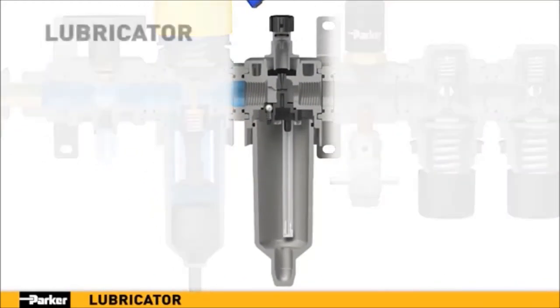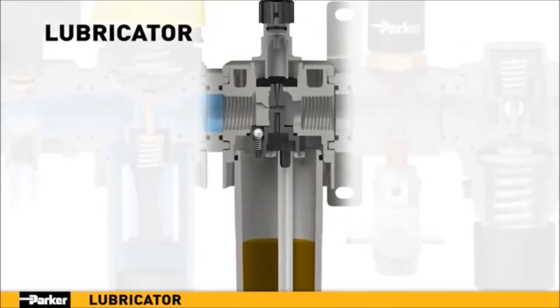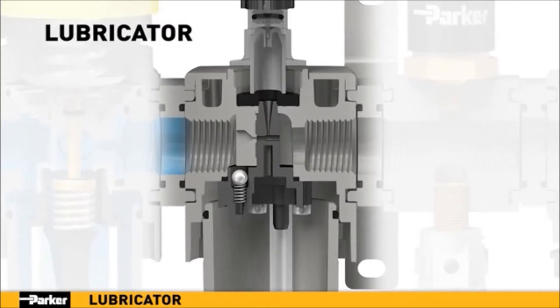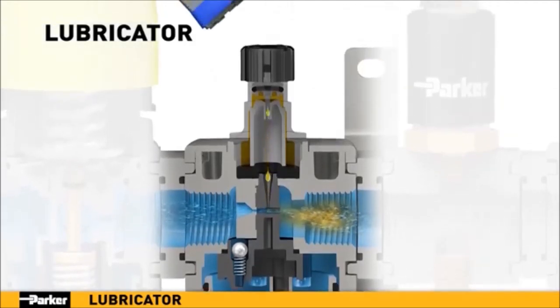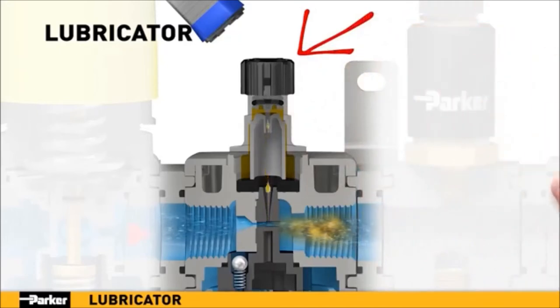Precision lubrication is essential for reliable operation of pneumatic components, and Parker's lubricator is engineered to deliver. When pressurized air is introduced into Parker's lubricator, it is guided through the body where the low pressure of the venturi effect draws oil from the bowl up through the pickup tube and into the dome assembly. From there, the oil is drawn down into the airflow as an aerosol, providing critical lubrication to components downstream. A hand-adjustable metering screw on top provides precise control over the drip rate.